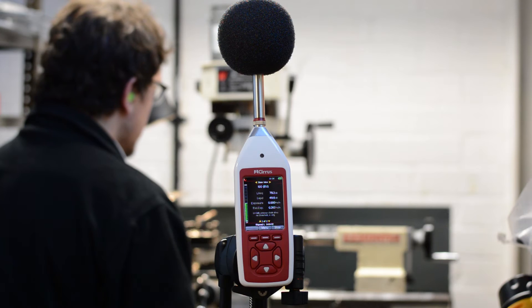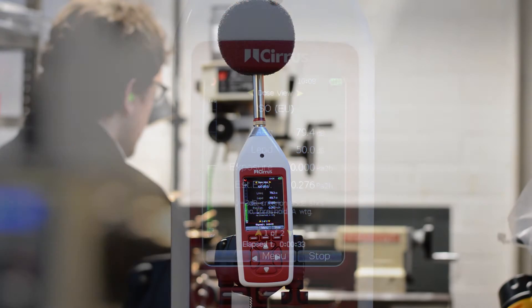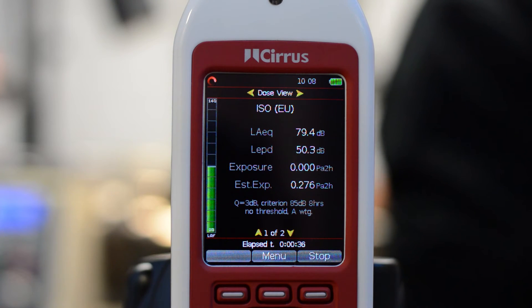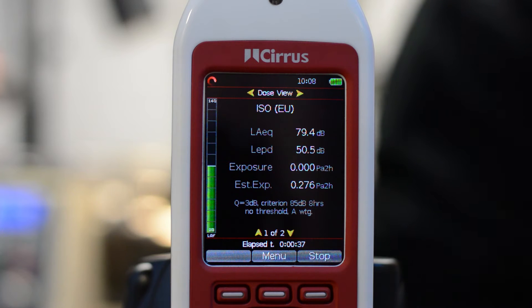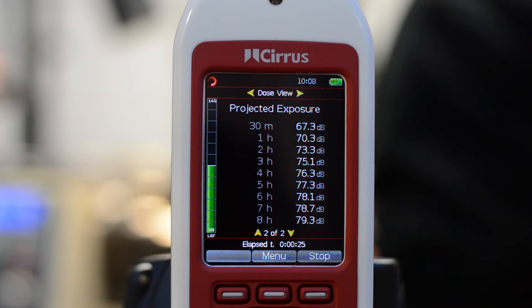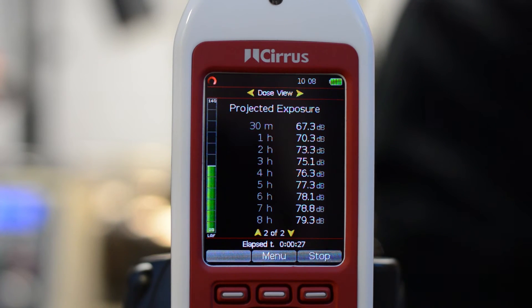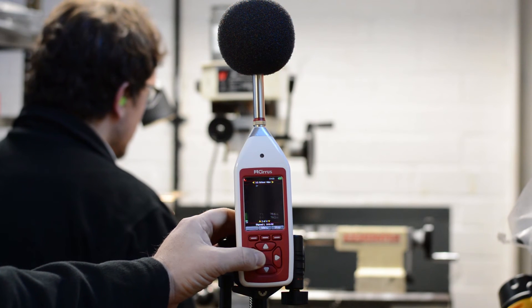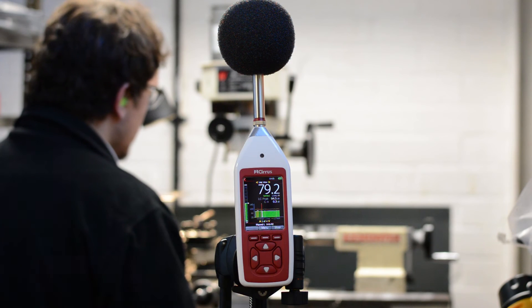Pressing the right hand arrow key again will move to the noise exposure or dose view. Press the down arrow button to view the projected exposure information. Use the left and right arrow buttons to move between the different information screens.